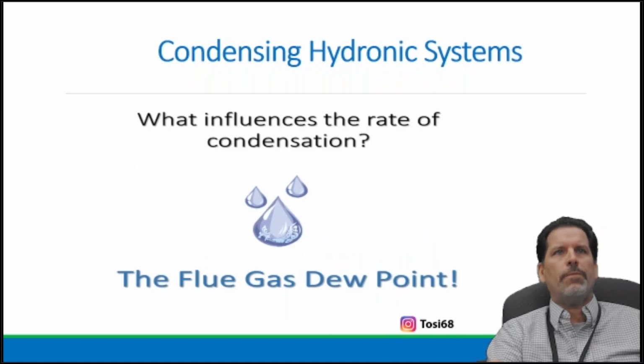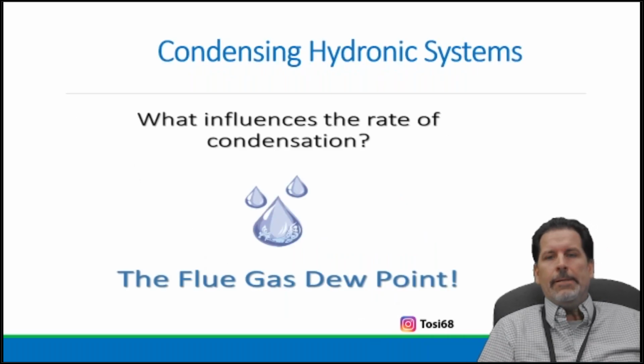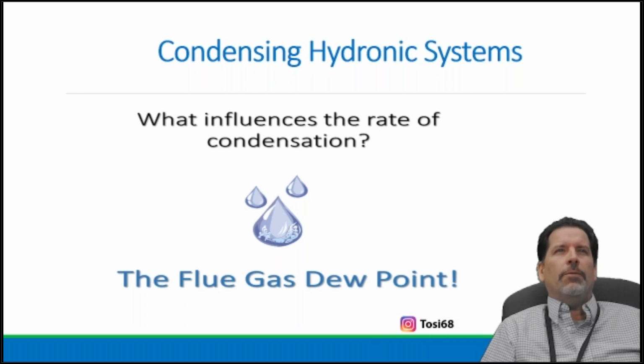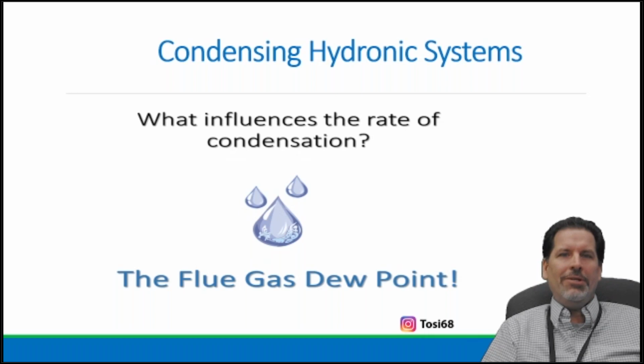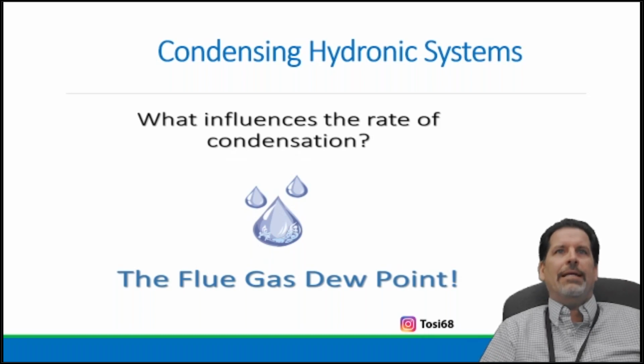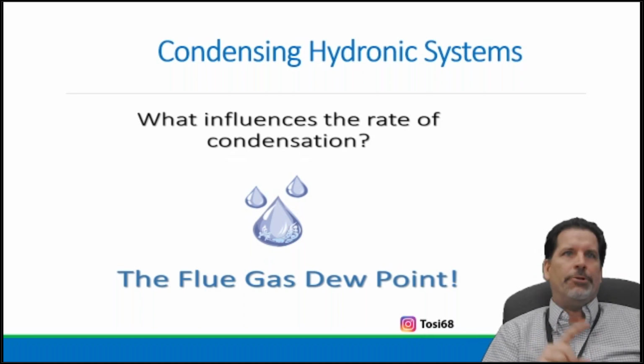Condensing hydronic systems, right? I thought this was interesting, I played with this term. What influences the rate of condensation? We always focus on the boiler, it's a condensing boiler, it's a condensing boiler, but is the system allowing the boiler to condense? That's the difference. We can hang something on the wall, have a leak-free system and think we're a hero, but did we actually construct or build this condensing hydronic system? Again, it comes down to sizing, selection, and water temperature.